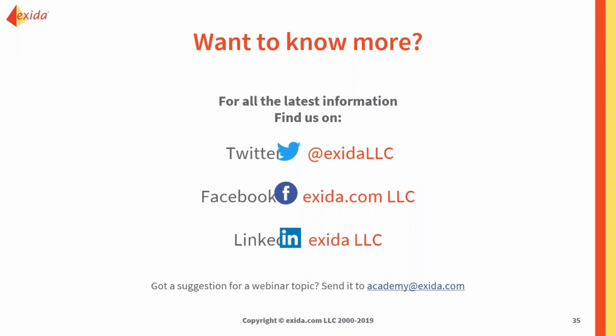The next question we have: is it okay to mix handbook data and manufacturer's data within one FMEDA? I wouldn't mix it within one FMEDA, but I would use it to compare. So I would do an FMEDA with all one component handbook or one component database. Then I would compare that FMEDA to other data books. If you are offshore or subsea, OREDA is a great one if you can match up the bounds the same. So I wouldn't mix within one FMEDA, but I would use that FMEDA to compare.